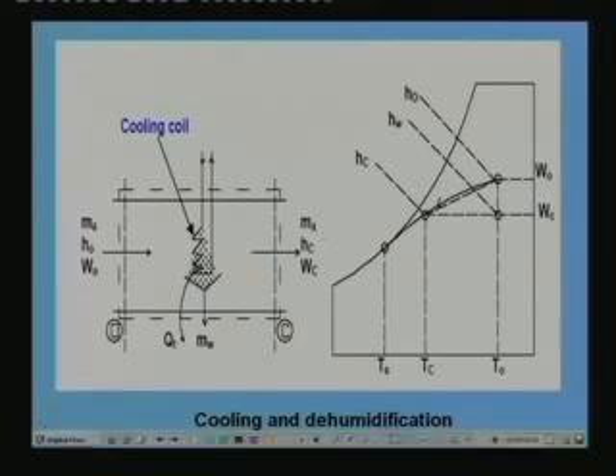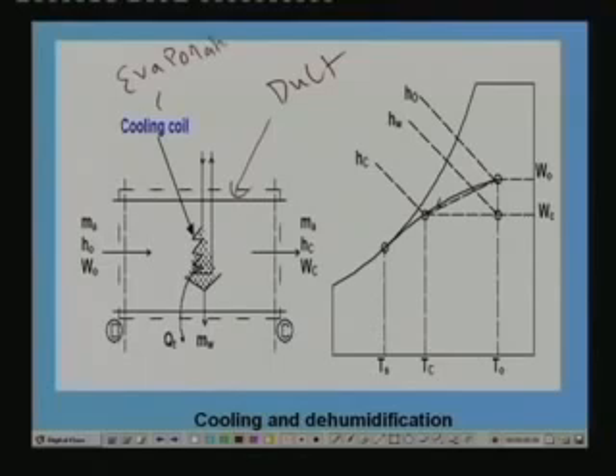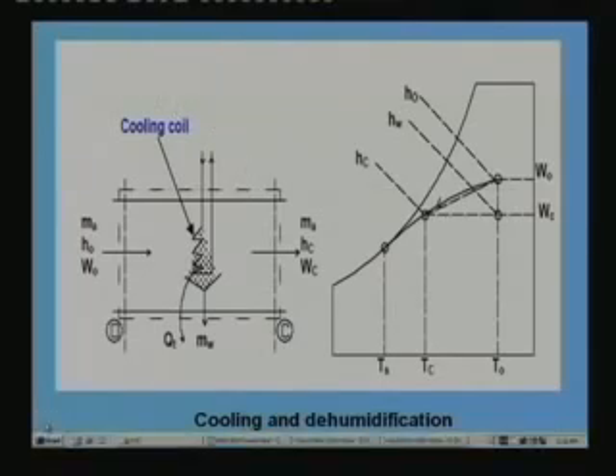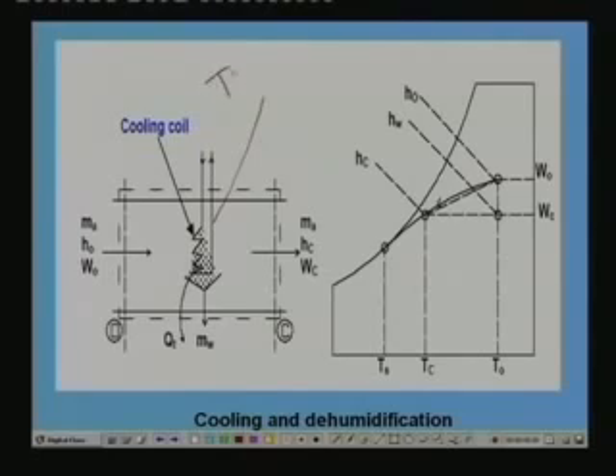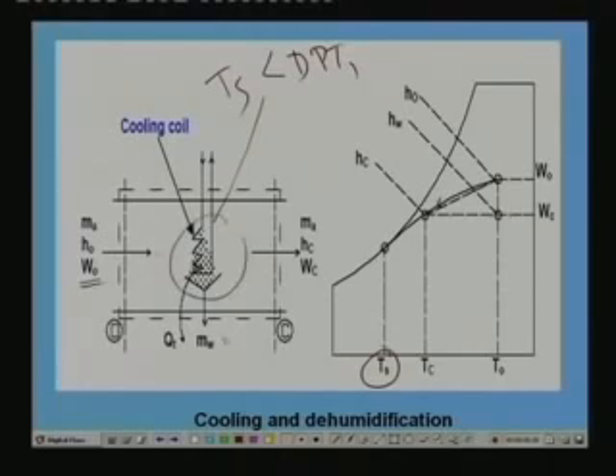For example, you can see here, let us say that we have a cooling duct. This consists of a cooling coil here. For example, this cooling coil could be the evaporator of a refrigeration system, that means refrigerant flows through this coil, or it could be a chilled water coil, that means chilled water flows through this. The surface temperature of the coil is Ts, as shown here. Ts should be lower than the dew point temperature of air. When it is lower and the air comes in contact with the coil, some of the water vapor condenses and leaves in liquid form.